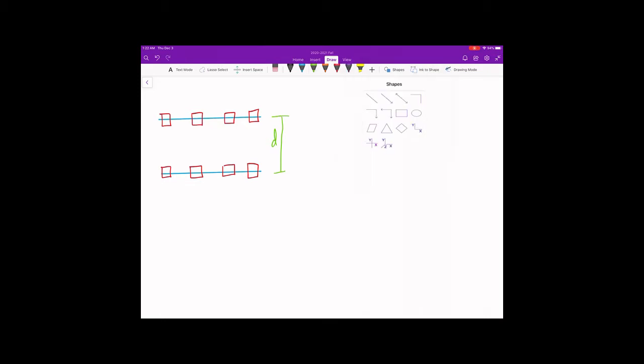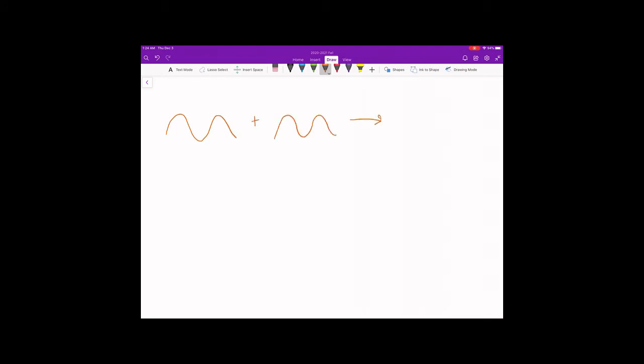When an X-ray hits an atom, its electrons absorb the energy, then emit another X-ray with the same energy in a process called elastic scattering. In a crystal, atoms are spaced into regular arrangements on planes separated by distance d, which is the same order of magnitude as the entering radiation's wavelength. X-rays are scattered by these evenly spaced atoms. When the angle between the incident and scattered X-ray beams reaches a certain value, constructive interference occurs and the signal is amplified. Bragg notated this mathematical relationship as 2d sine theta equals n times lambda.